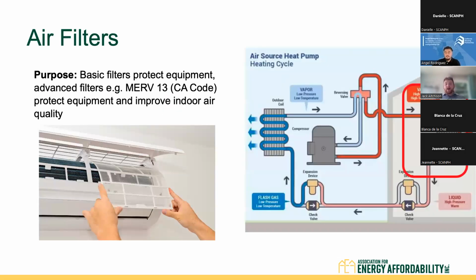So air filters, the purpose of an air filter. We have two levels of air filter types. We have our basic filters that protect equipment. We have our advanced filters, which are MERV 13, which is California code. Those are going to protect your equipment and improve indoor air quality. Looking at that diagram of all of the heat pump components, that's what goes in a heat pump. Over on the right, you can see that red box. That is where your air filter is going to be located.